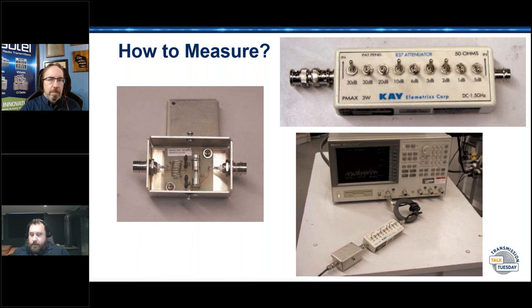If you can measure down to 80, and you're trying to use that full range, you'll have a better time if you can shrink the window up a bit. So we'll take the carrier down. I think our filter bottoms out around minus 42 or so. But that opens up a lot more usable window on the analyzer, and you can get a better sense of what's going on. Some of the more expensive ones are good for 100, so it's not really necessary.